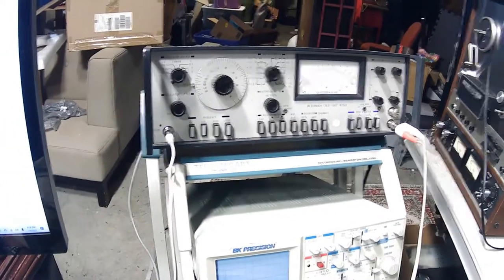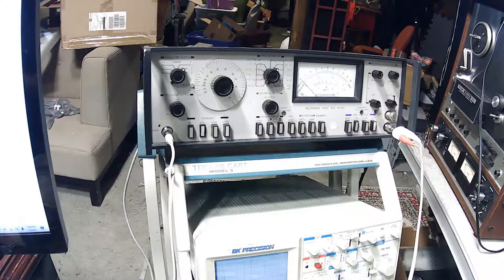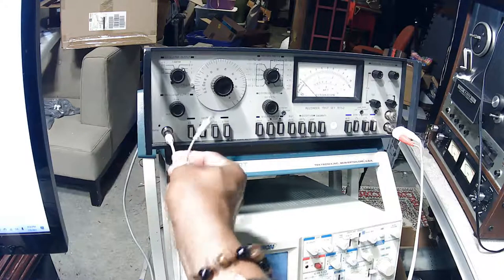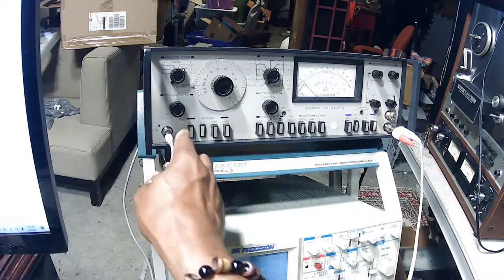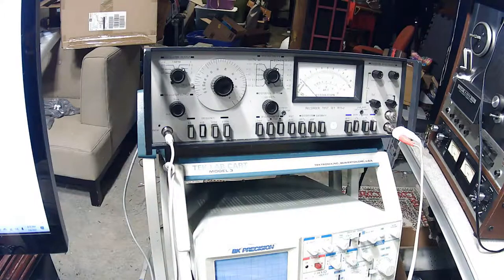Right now I have a 1 kHz tone at 0 dB applied to the 635D, and if I press the tape source switch, we'll read that 0 dB signal coming into the machine. Okay, and the goal now is to make the right channel. I'll do these one at a time. This is the left channel. I've done that one already. And this is going to be the right channel coming into the test meter.